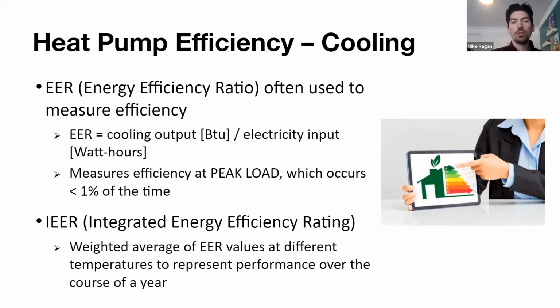But the thing with this is that your system is only going to be seeing a peak load less than 1% of the time. That's going to be the peak time of the summer months, where it's the absolute hottest, where every single indoor unit in your system is calling for full cooling at the same time. That's not a very common occurrence in the lifetime of a system, so that's not exactly the best metric to actually assess the efficiency of that system. Another metric we can utilize is the Integrated Energy Efficiency Rating, the IEER. That's going to take the weighted average of various EER values at different temperatures to represent the performance of the system over the course of the entire year.